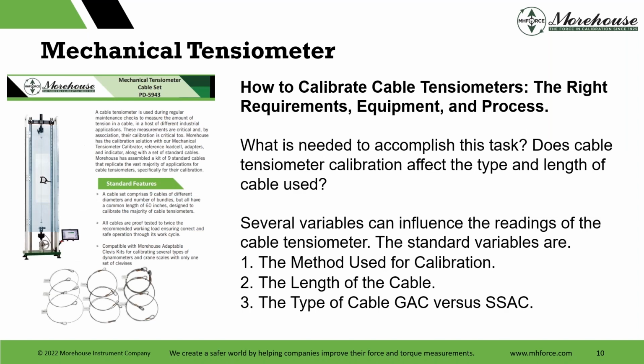So typically when we do anything, we deal with 3 things: the right requirements, equipment, and process. And then it's, what do we need to accomplish the task? Does cable tensiometer calibration affect the type and length of the cable used? Yeah. And then you have several variables in this case that can influence the readings. Standard are the methods used for calibration, length of cable, and the type of cable.